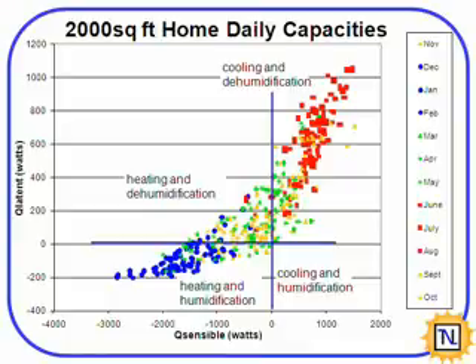So where we saw that the conventional system had a 10 kilowatt cooling capacity, this is very small. Heating-wise in the winter, about 3,000 watts are needed, and that's mostly sensible load, just bringing that temperature up. And then in this kind of house, we see in this area here, the origin is roughly, I think, 50% relative humidity, 72 degrees Fahrenheit. So spring and fall time, really not much conditioning is needed within this type of home.